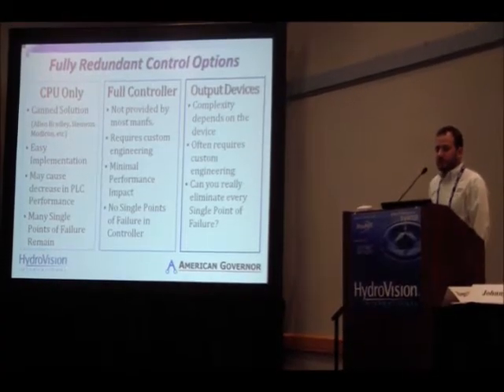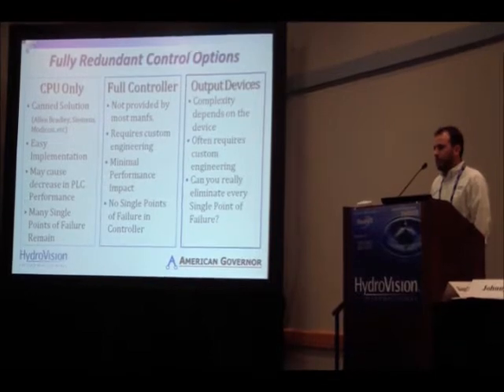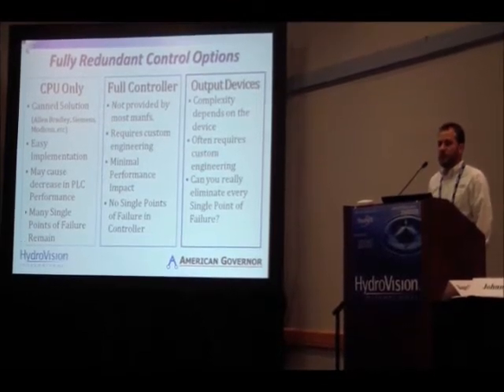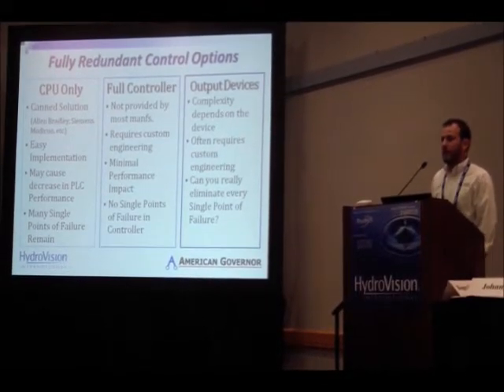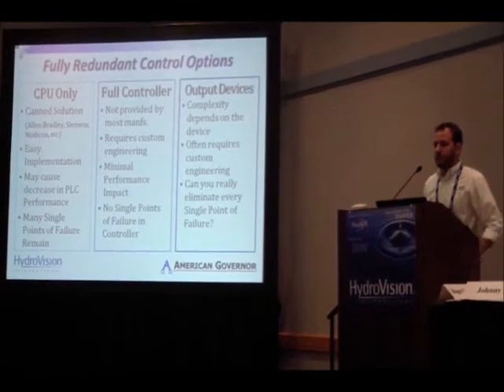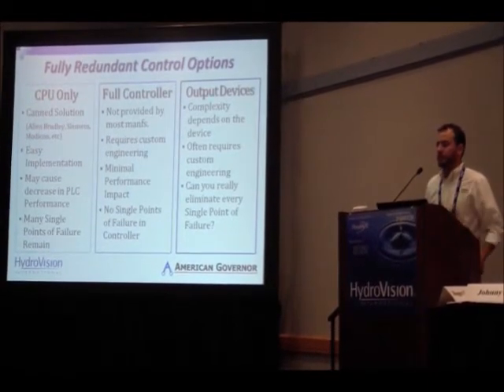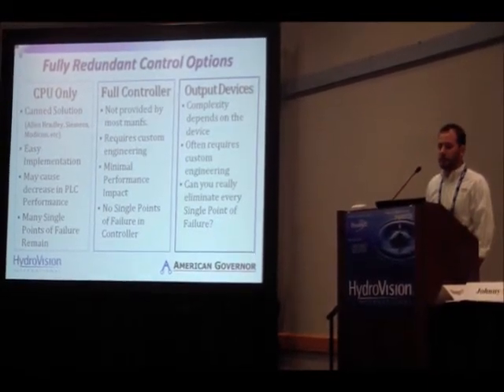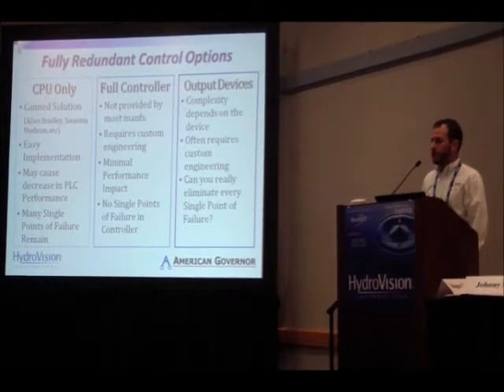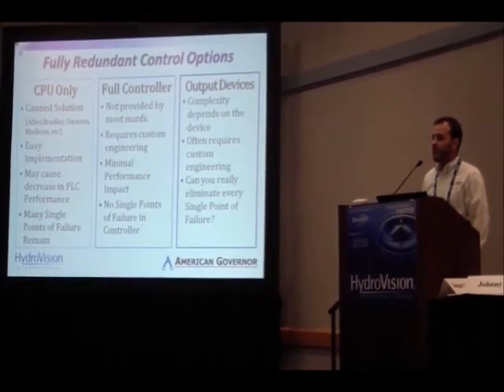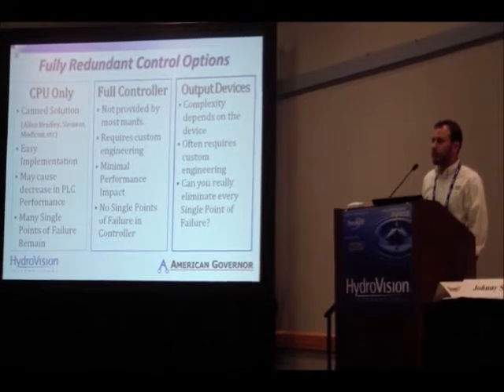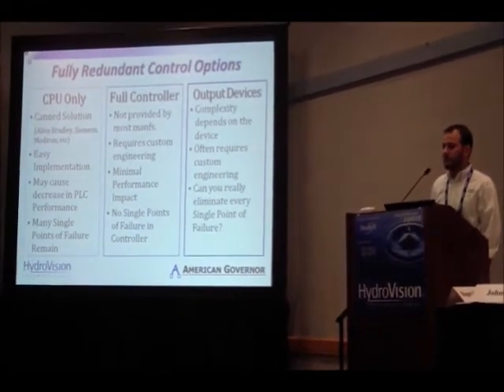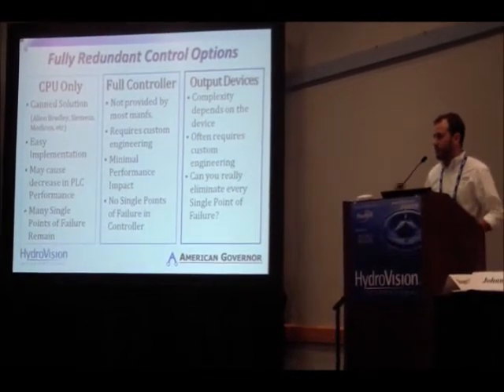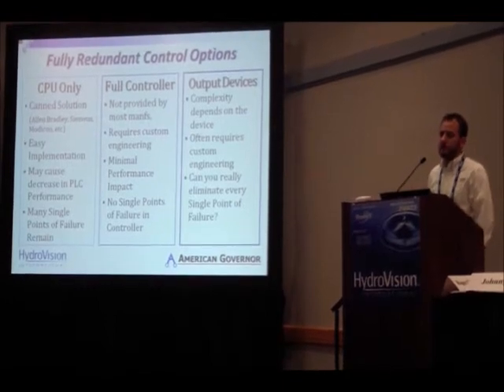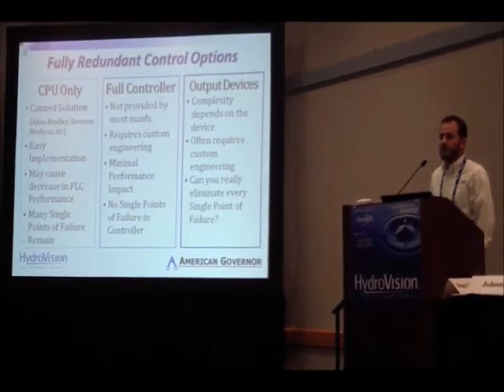So these three options. If anyone who's implemented a new control system, say you're going with an Allen Bradley controller and you want redundancy, the first thing you're going to look at is, well, what's their solution for redundancy? And most PLC manufacturers' solution for redundancy is CPU only, which is one of the things that's attractive about it. It's a canned solution. It's easy to implement. You pretty much plug and play the components, select the box and the software that you want redundancy, and there you have it.